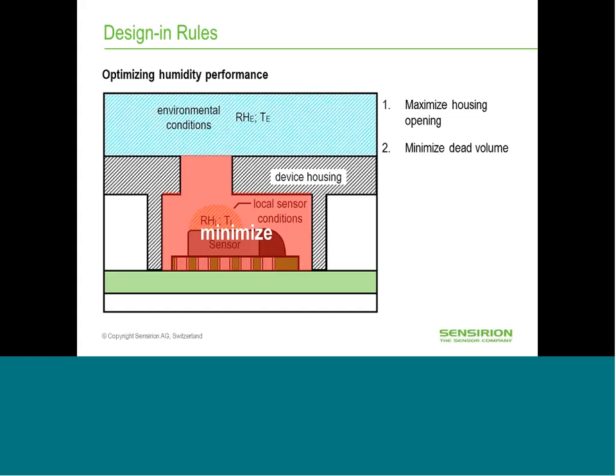Then the next thing is to minimize the dead volume. When we talk about dead volume, we mean the volume that the sensor is located in behind the opening. If we have a change of environmental conditions, the conditions in this whole dead volume need to adapt to the environmental conditions so the sensor can actually measure the new environmental conditions. The larger this dead volume is, the longer this will take. So if you want a quick response time, you really have to minimize the dead volume the sensor is located in.